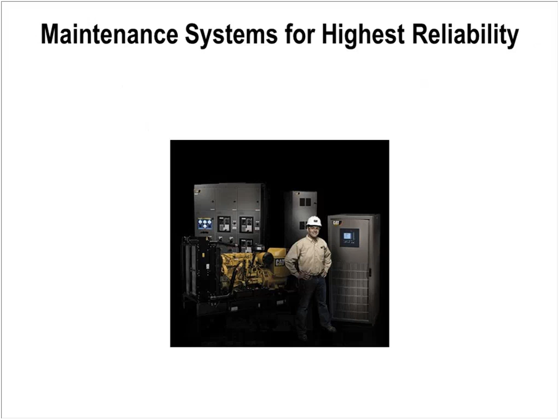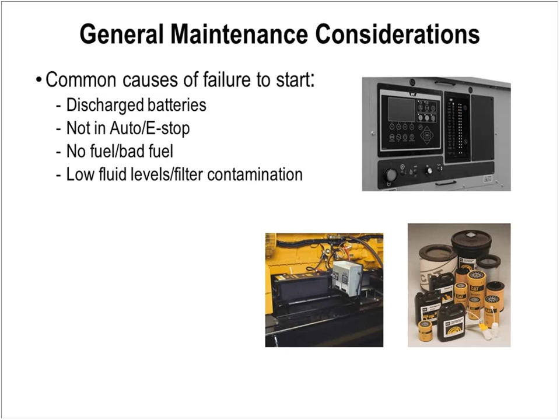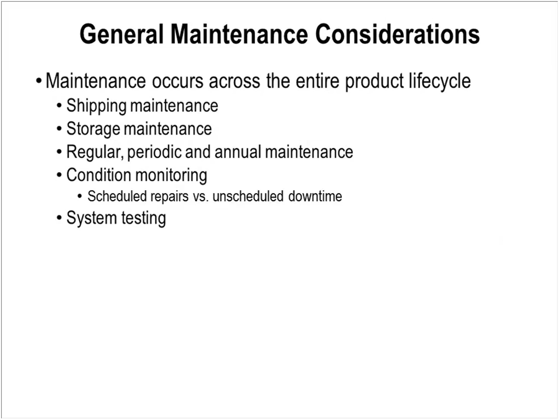Maintenance considerations—I want to touch on this quickly. If you don't maintain your systems, they're not going to work well. The major reasons we see these units not operating is because the batteries are discharged. You can't tell you how many times we see systems not in auto, or with bad or contaminated fuel.